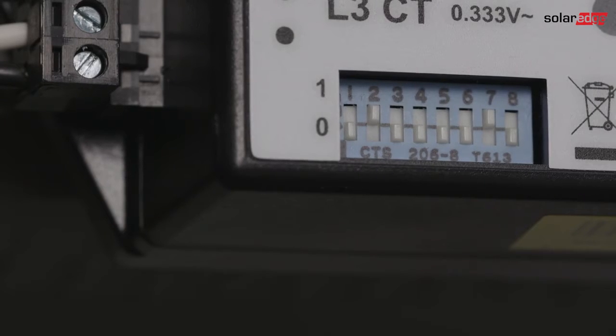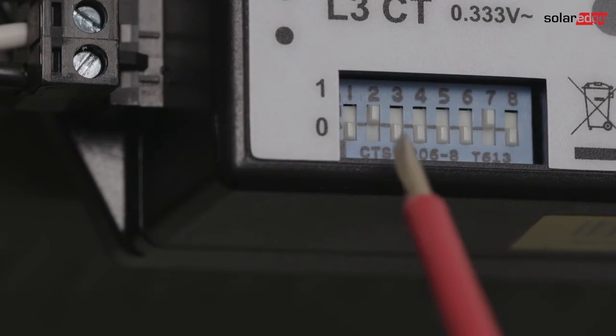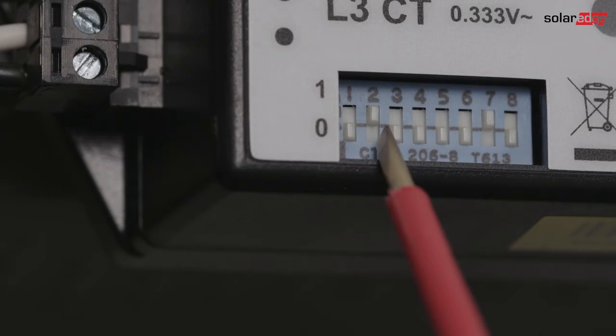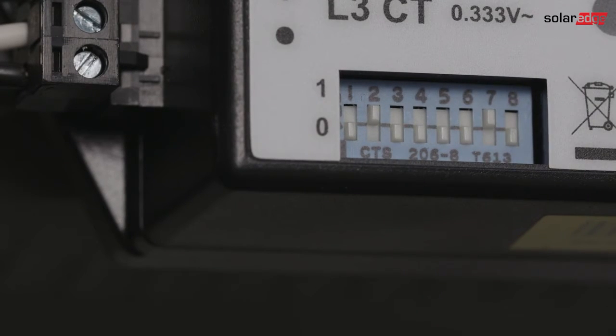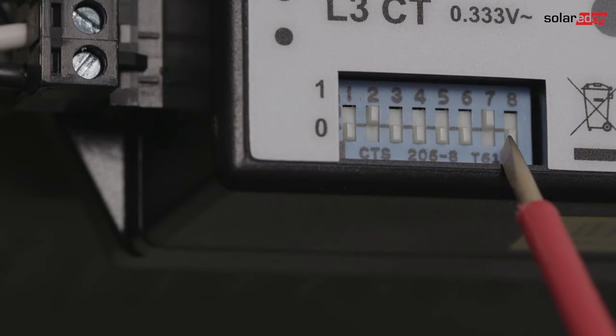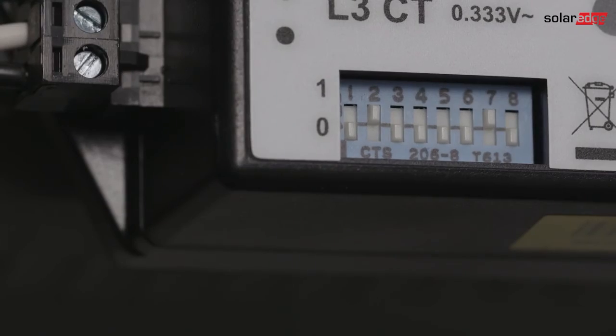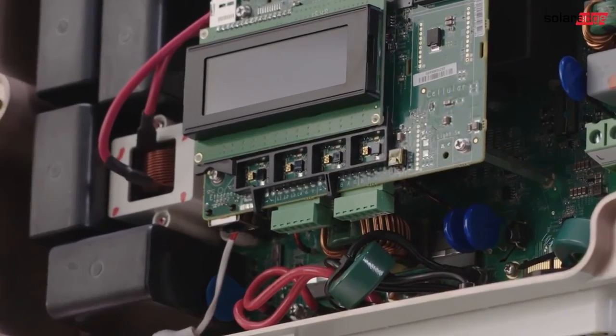Now we need to configure the meter. Dip switch number 2 needs to be up, which is the on position, to assign device ID 2. If a meter with a WND part number is the first or last device on the RS485 bus, move dip switch 7 up to terminate the bus. Otherwise, use the inverter termination.